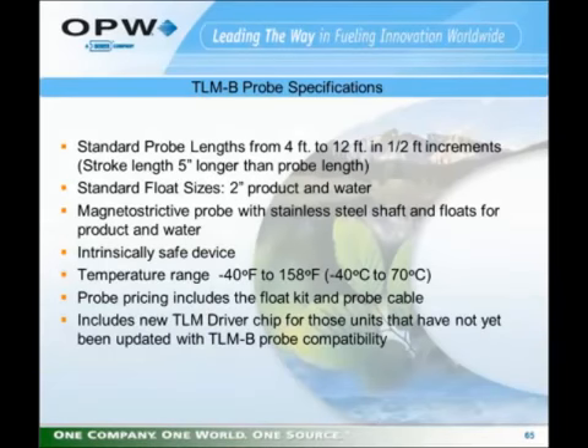Probe specifications. The TLMB probe can be purchased in lengths from 4 feet to 12 feet in half-foot increments. The probe is labeled with a stroke length. That stroke length is 5 inches longer than the nominal probe length. So if there's confusion about ordering a probe, look at the model number that's on the existing probe that you want to replace. Look at the Q0400-408, which would be an 8-foot probe, 96 inches. The stroke length would be 5 inches longer than that, which would be 101 inches. So be cognizant of the fact that the stroke length is actually longer than the nominal length.